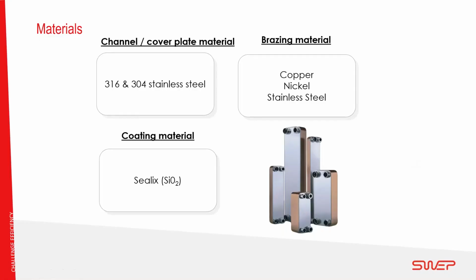So just covering a little bit more the materials that we use, mainly it's stainless steel 316 and 304 for the channel and the cover plates. Brazing material, predominantly copper, but for more demanding applications, for example, if there's corrosive fluids, aggressive gases and so on, then we also have the option of looking at nickel brazed and stainless steel brazed as the brazing material. An example of this could be ammonia heat pumps, where the copper brazing would be corroded pretty quickly. So we generally have to look at stainless steel in this kind of application.